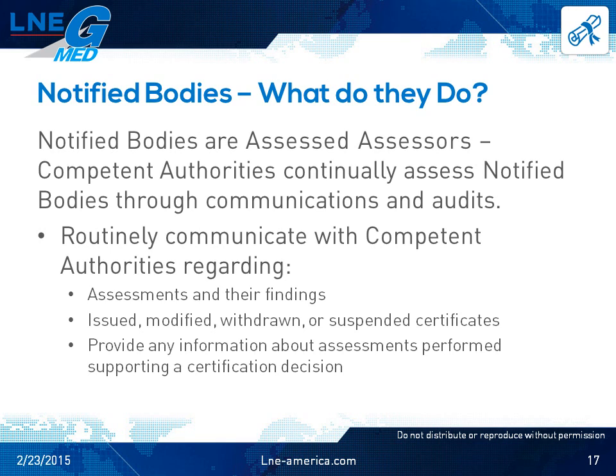Now, during a witness audit, the competent authority is focused on how the notified body conducts the audit and what it audits. Notified bodies are in constant communication with competent authorities regarding the assessments that they perform and their findings, the certificates they issue or withdraw, and to provide information about any assessments they performed to support a certification decision. So, just as notified bodies assess medical device manufacturers, competent authorities assess notified bodies.